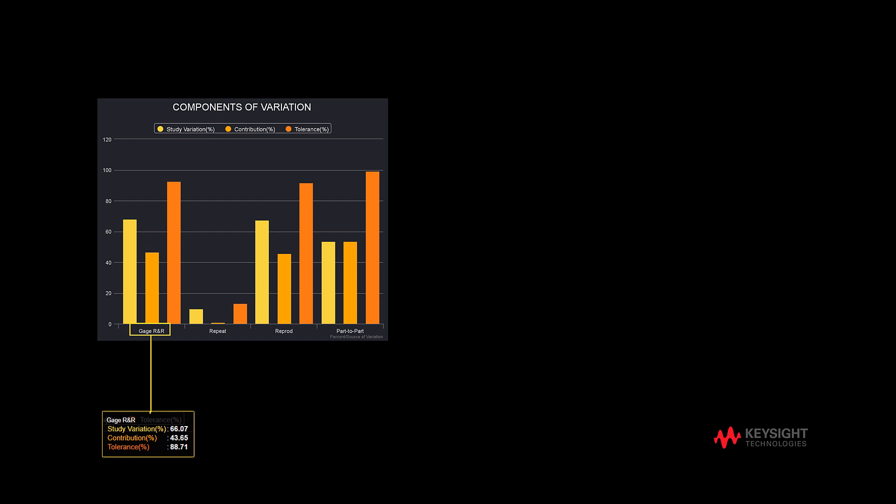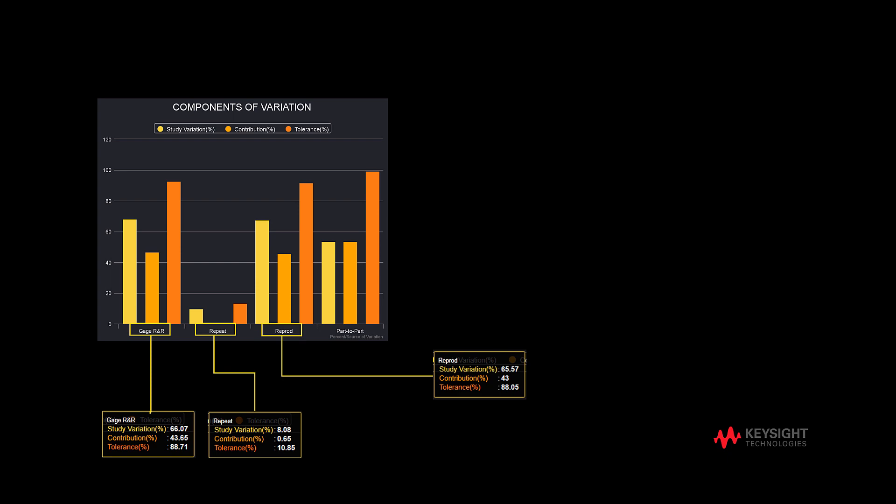The other sets of bar charts provide the same information on study variation, contribution, and tolerance for repeatability, reproducibility, and part-to-part variation respectively. A good measurement system should not exceed more than 10% of total variance.